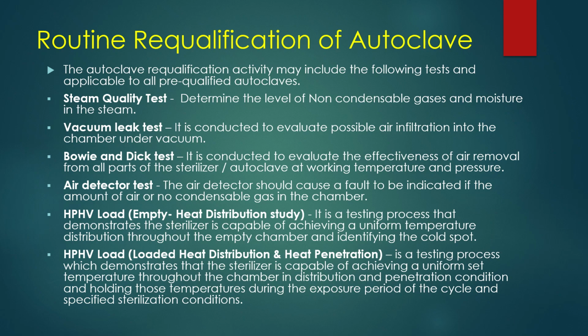Next one is HPHV load, that is empty heat distribution study. It is a testing process that demonstrates the sterilizer is capable of achieving a uniform temperature distribution throughout the empty chamber and identifying the cold spot. Next one is HPHV load, that is loaded heat distribution and heat penetration study. It is a testing process which demonstrates that the sterilizer is capable of achieving a uniform set temperature throughout the chamber in distribution and penetration condition and holding those temperatures during the exposure period of cycle and specified sterilization conditions.